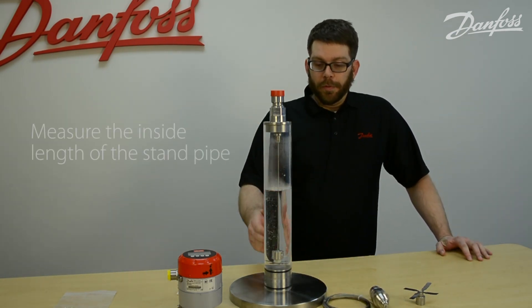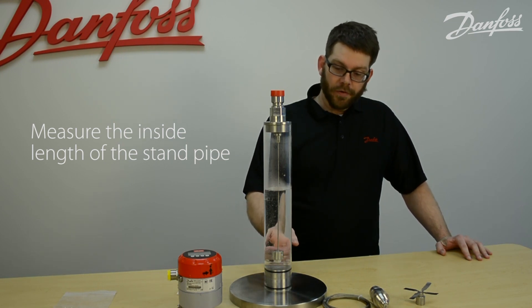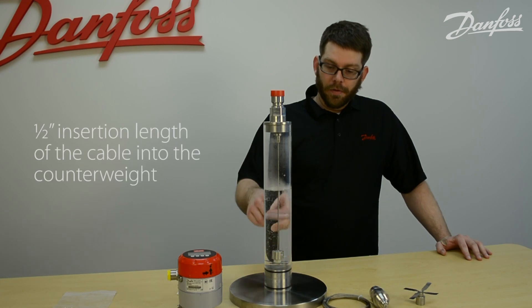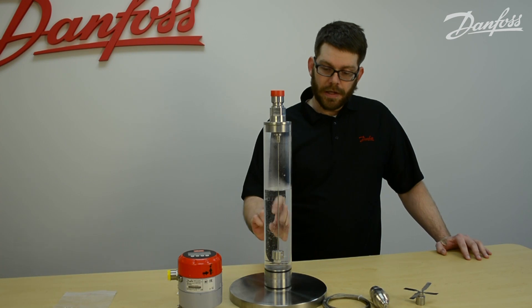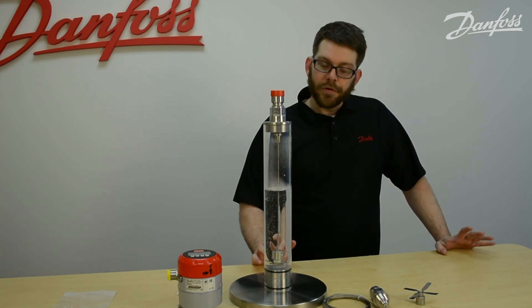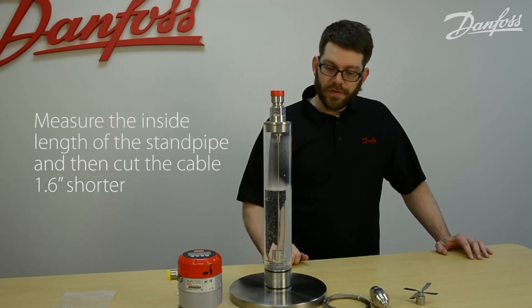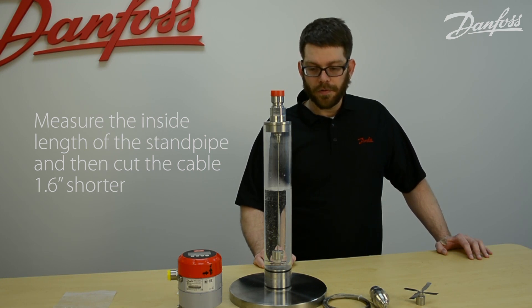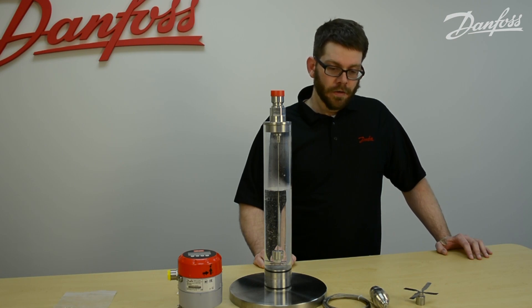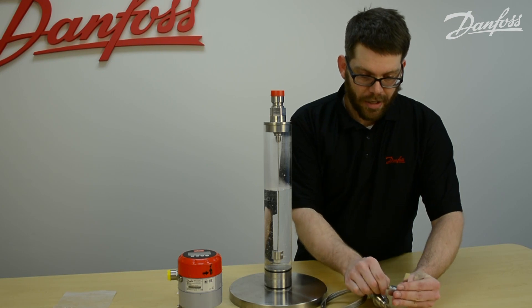At this point we would measure the inside length of the standpipe. We want to leave 0.8 inches of clearance off of the bottom. There's a half-inch insertion length of the cable into the counterweight, and the counterweight is 1.3 inches tall. After you do all the math, basically what you want to do is measure the inside length of the standpipe and then cut the cable 1.6 inches shorter than what the inside length of your standpipe is.